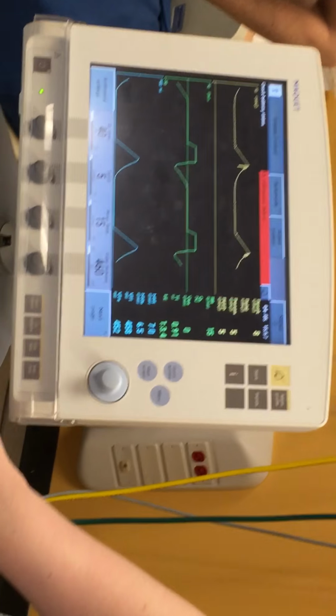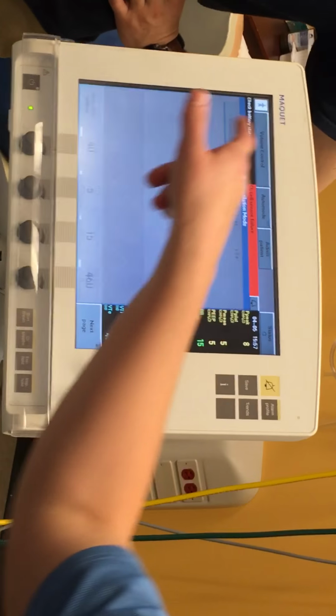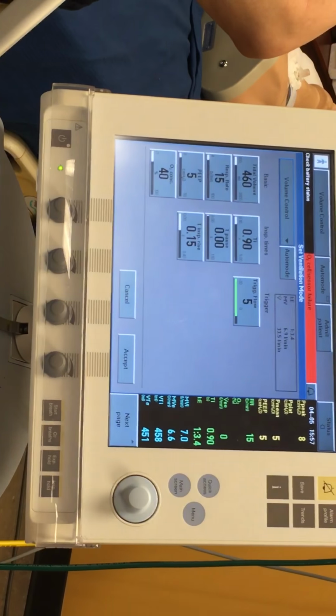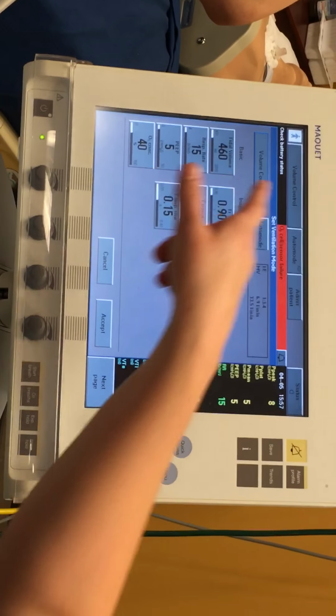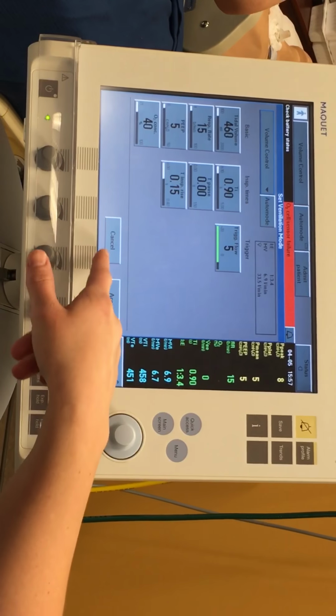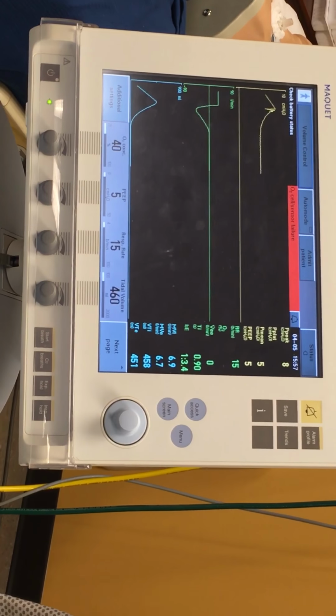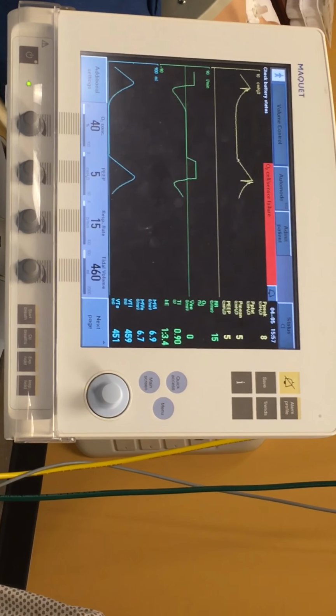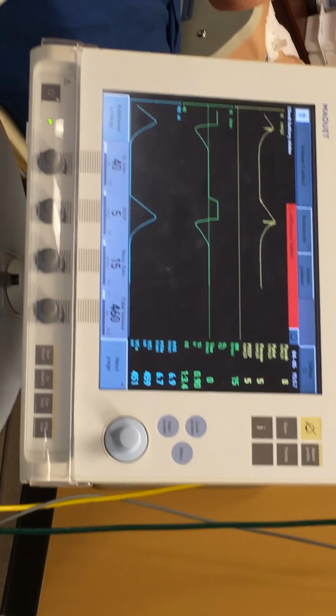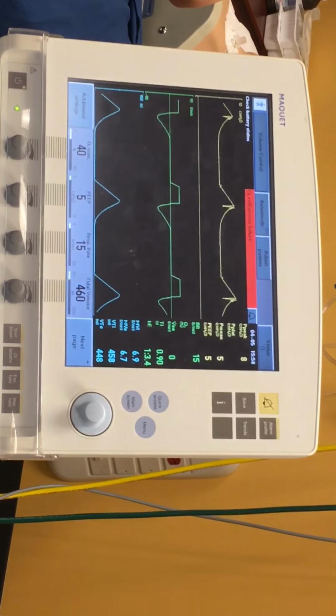Oh, okay. Isn't there another breath hold button? You can do breath hold down here, but this one will automatically default to like 0.4 seconds T-pause. What's inspiratory rise then? That's how fast the gas is being delivered. It's your rise time, and just leave it at 15, pretty much always, unless you have a patient that's just really air hungry. Okay. And then the 0.9, right?